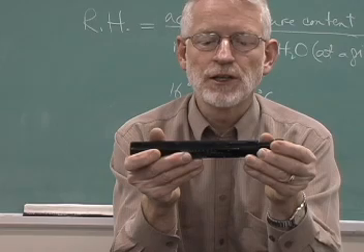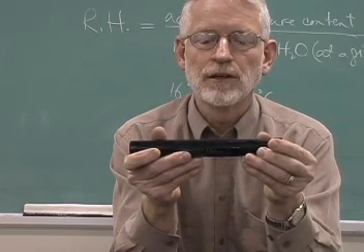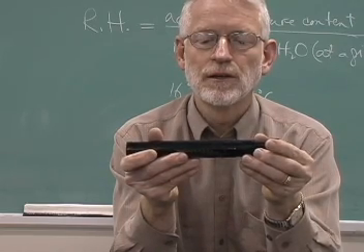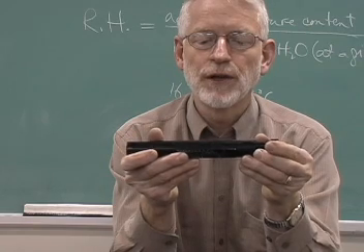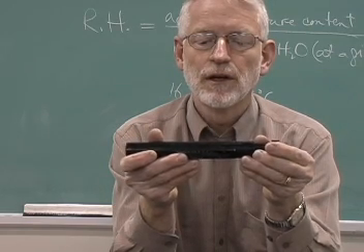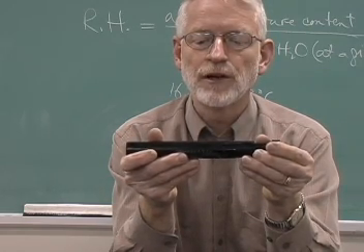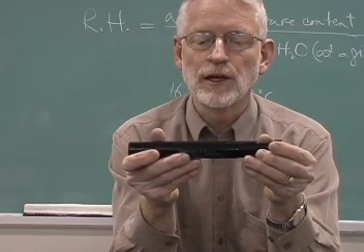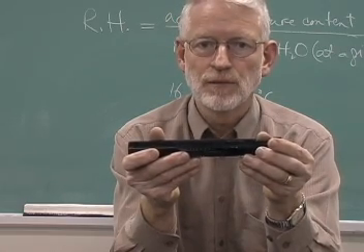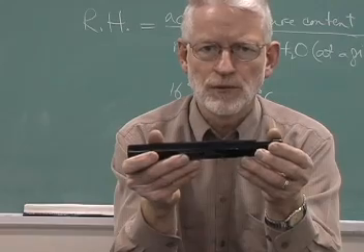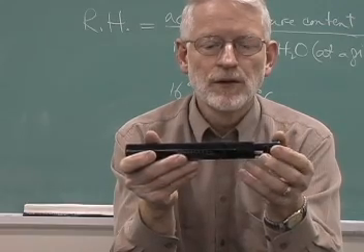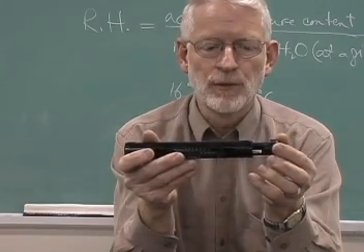So we had 16 degrees and 23. So we have the wet bulb and the dry bulb together, and that gives me a relative humidity of about 48%. Very close to what we had before. So this is called a Sling Psychrometer.